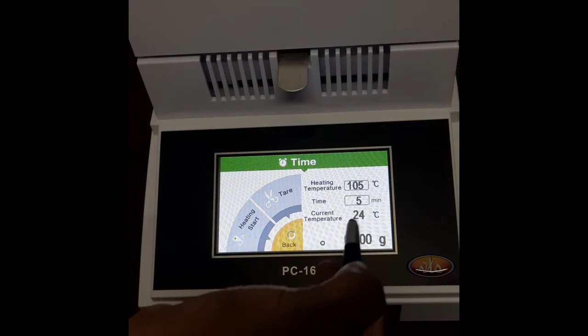In auto heating mode, we don't need to enter the time, only the heating temperature. Time it will select automatically, and whenever there is no weighing difference, it will stop the heating, and it will give you the moisture percentage. In the history record, you can see the previous records. The history record will come like this.